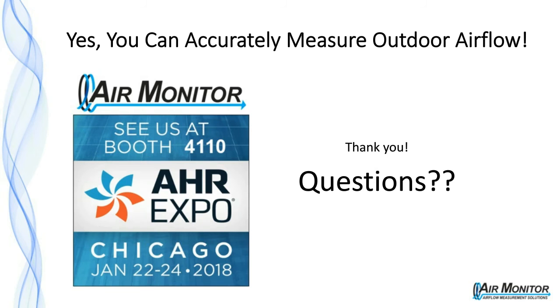The next question is, the dual transducers that are on board the system, are you able to field calibrate, zero and span by your own technician, I assume in the field? With the proper tools, absolutely. We're dealing with very low differential pressure, so you have to make sure that you have a capable digital manometer to perform that. With the zero calibration, I mentioned Auto Zero previously, and Auto Zero takes care of the zero calibration at least once a day.